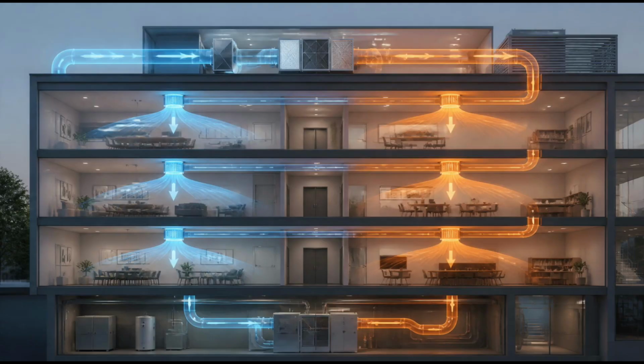Gentle circulation helps prevent stale air from settling. Even in fully unoccupied spaces, a minimum level of airflow is often maintained. This gentle circulation keeps the indoor environment fresh enough that when people return in the morning, the air does not feel stale or heavy. It also helps prevent any temperature stratification, the tendency of warm air to rise and pool near ceilings while cooler air settles near the floor, from becoming pronounced.